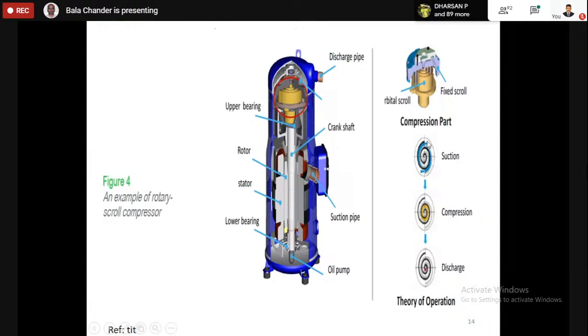Okay, you can see initially the outer scroll and the gap between the two scrolls. You have some space here. As I said, it is a positive displacement. Volume reduction happens, then the high pressure fluid is moved into the next scroll, and then finally it is discharged. This is the volumetric efficiency of the scroll compressor. It will be above 90%. Okay, above 90%.